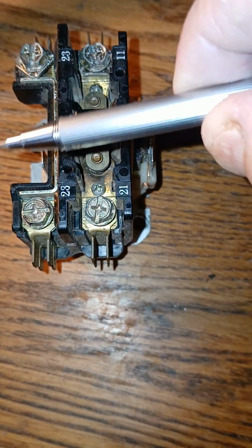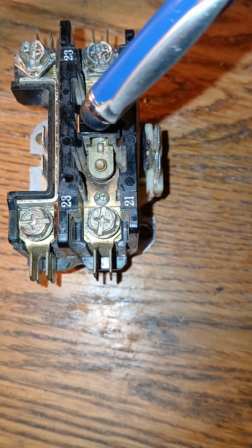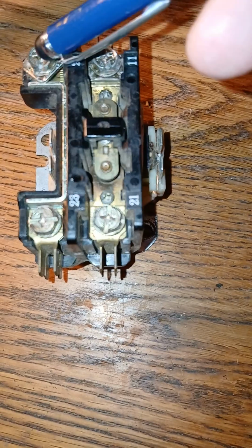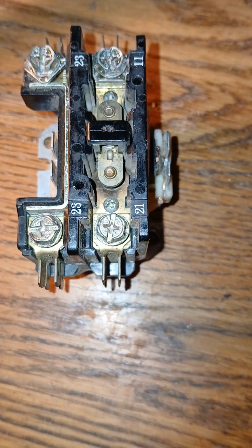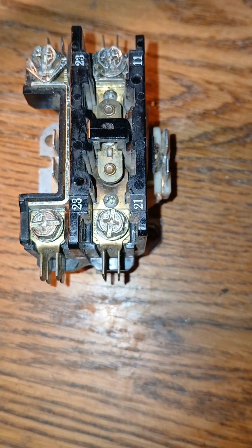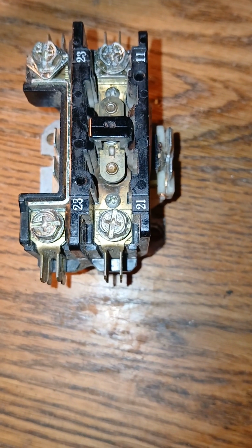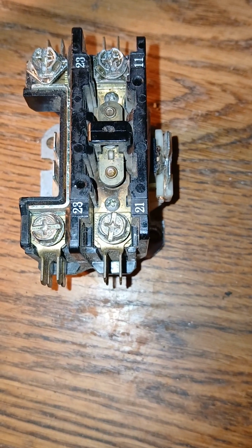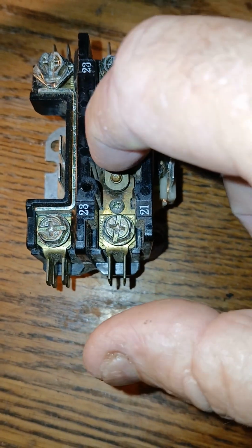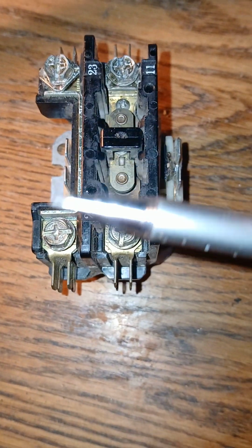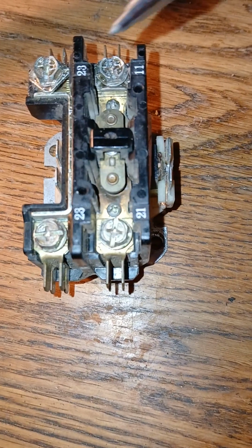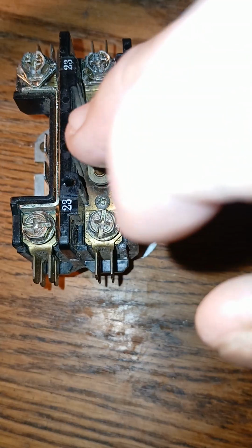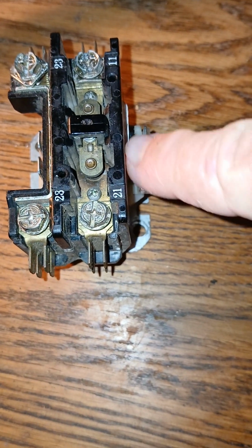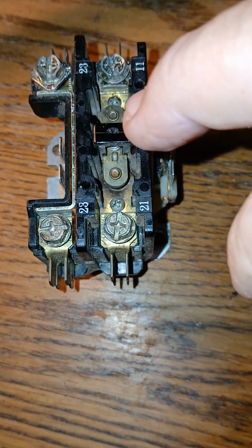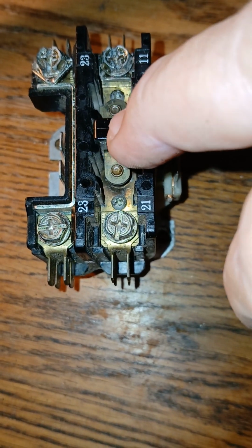But basically, when it becomes energized from the thermostat, once this becomes 24 volts, hits here and here, then this pulls in. Once this pulls in, then your 120 jumps from here to here. Now, when it becomes de-energized, say if you were cooling your house and you had the thermostat set on 70, and then it met the temperature in the room, and the thermostat cut off because it was satisfied, then this little plunger, kind of a spring-loaded little gadget, would pop up, and then you would only have 120 here, 120 here, and you would not have 120 here until it becomes energized again by the 24 volts, which is on this side and this side. And once the 24 volts energizes this side, it pulls the coil in and maybe creates, I'm not certain if it's a magnetic field, and pulls this down.